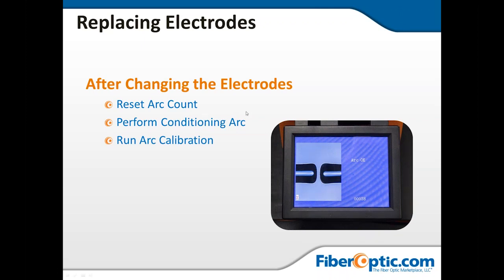Because remember, everywhere you go, if you go from outside to inside, that machine has to be acclimated. So if you're outside and it's cold, and you come inside and it's at a comfortable temperature, you have to do an arc calibration until that machine is acclimated to the conditions that it's working in and you are working in.